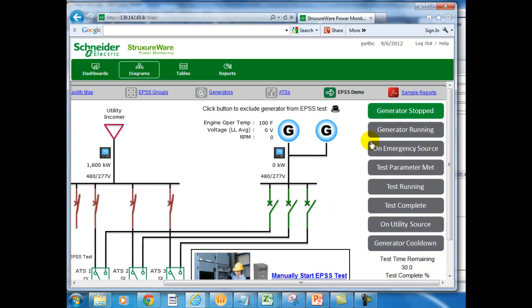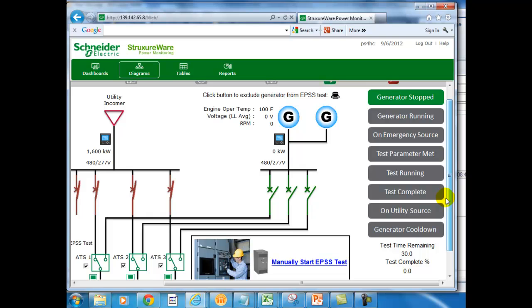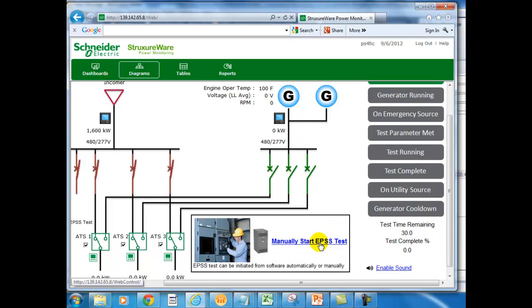So here are the stages that you would expect to see in a generator run. You would expect to see the generator fire up. You will see the transfer switches operate and move to the emergency source, run the load bank for a while, and then switch back. So let's go ahead and do that. This is a 30-minute test which is simulated in 30 seconds. So you can see the generators firing up.